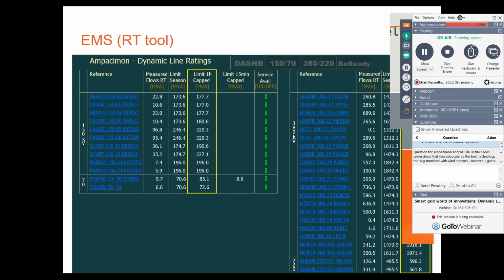And this is just to show you in real time in our SCADA system. You see all the lines are equipped, and in the yellow box you have the Ampacimon gain, and this automatically replaces the static rating. So the static rating is replaced by the dynamic rating constantly, continuously, and the N-1 analysis, the security analysis, is done with this value. So we are totally trusting the technology, and this is fully automatic. So for the operator, it's manageable also, because he has 30 lines that have to be automated. So the line might be in overload with respect to the static rating, but the dispatcher might not see it because Ampacimon says this is fine, you have enough margin, and so it will not be polluted with a fake incident. So that's how we do it.